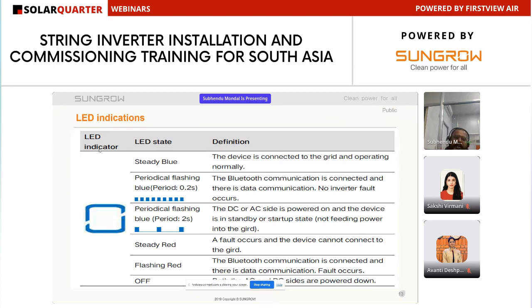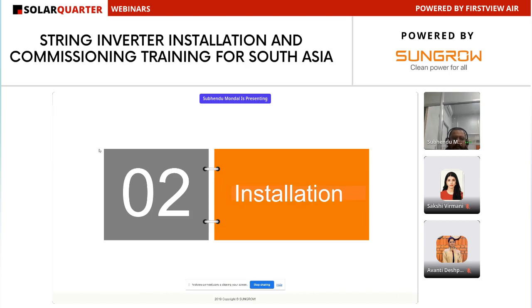Then it's steady red. While the inverter LED is steady red, that means the device is not connected to the grid. If any fault occurs, we can check by connecting the app to see which fault has occurred. We'll discuss this in upcoming slides. Flashing red means Bluetooth communication is connected, and there is data communication. When a fault occurs, it will flash, and it will be off while there is no AC power and no DC power. At that time the LED will be fully off. So I am going to the next topic, installation. I'll present a short video and I will explain after the video.